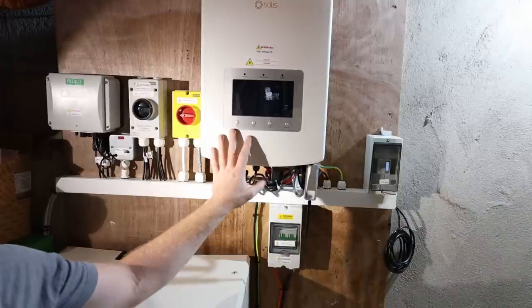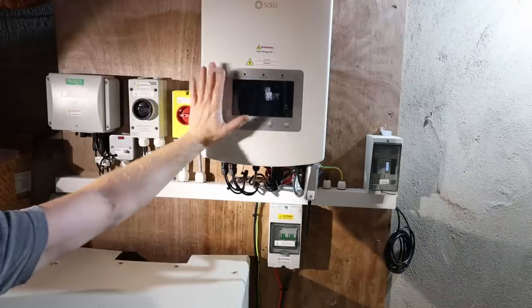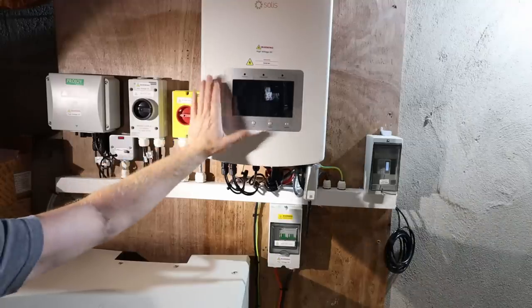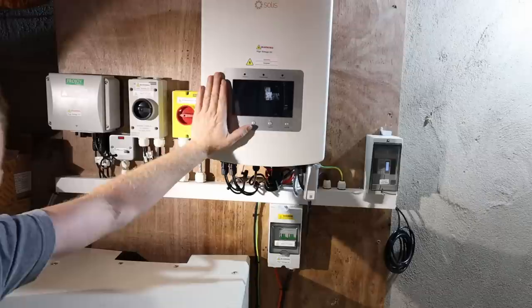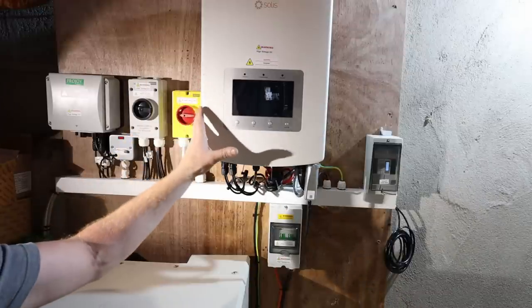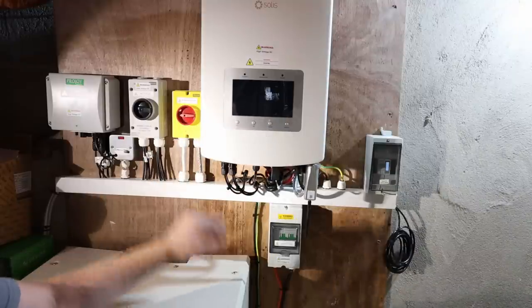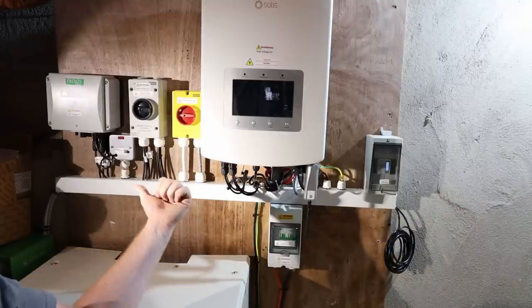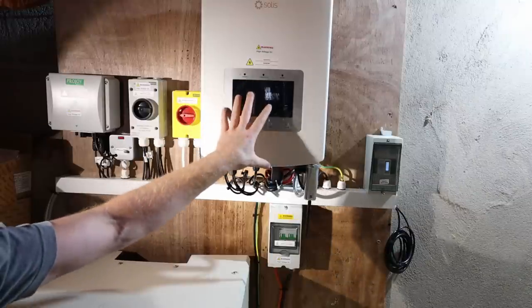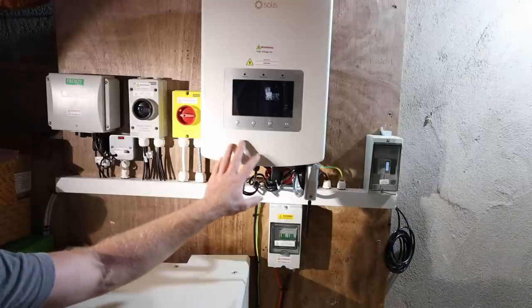Moving over to this side, here's the main inverter — the Solis, a 6kVA inverter. As explained, you cannot have more than a 6kVA inverter in a domestic single-phase situation in Ireland, or 11kVA three-phase. No more than that can be fed back to the grid. It doesn't matter how many panels I put on my roof — this inverter will never send more than 6kVA back. It also conforms to all the regulations for disconnection times for over-voltages and under-voltages.